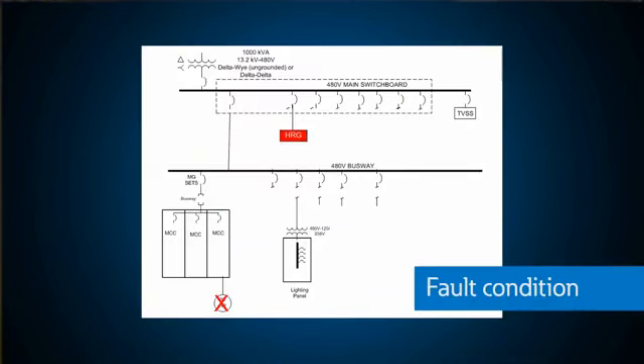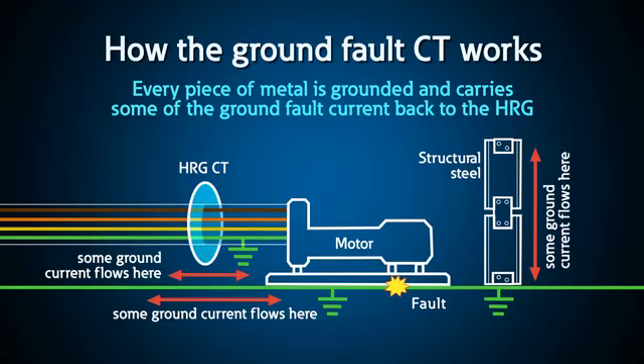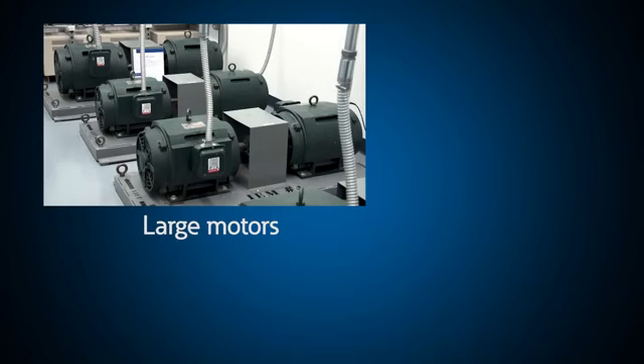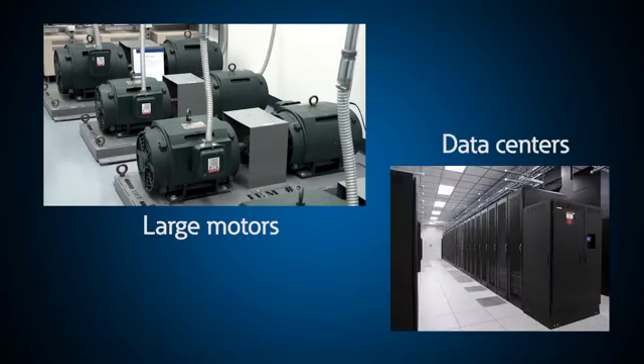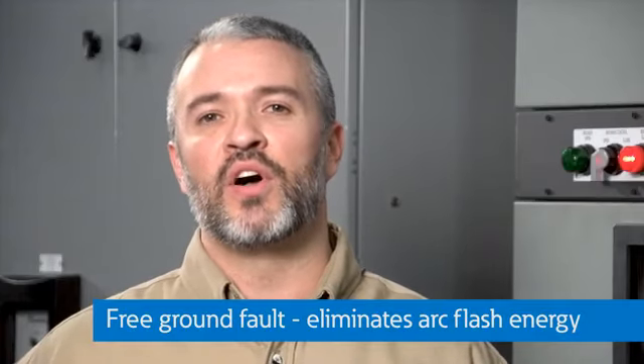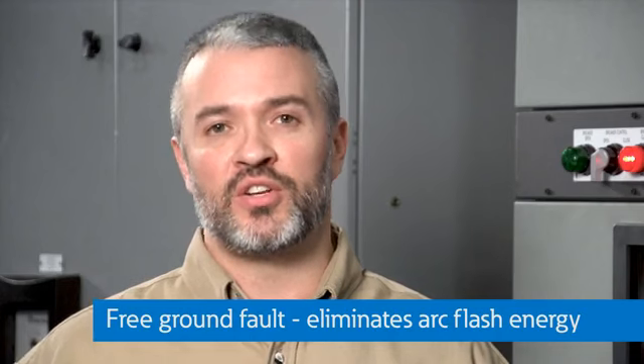Operators are alerted to faulted conditions and can easily locate the ground source via built-in fault tracing. High-resistance grounding is typically used on industrial power systems that have many large motors, and more recently is used on data centers where large three-phase UPSs are the major loads. These systems allow for a free ground fault with no release of arc flash energy.